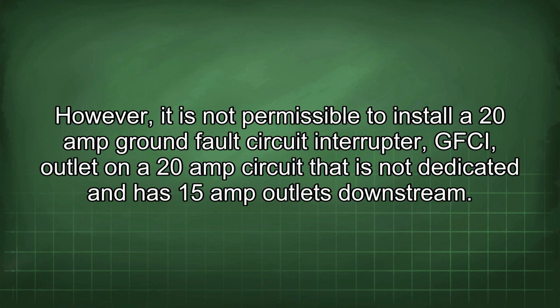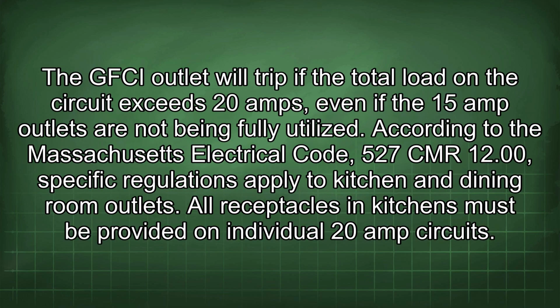However, it is not permissible to install a 20 amp ground fault circuit interrupter (GFCI) outlet on a 20 amp circuit that is not dedicated and has 15 amp outlets downstream. The GFCI outlet will trip if the total load in the circuit exceeds 20 amps, even if the 15 amp outlets are not being fully utilized.